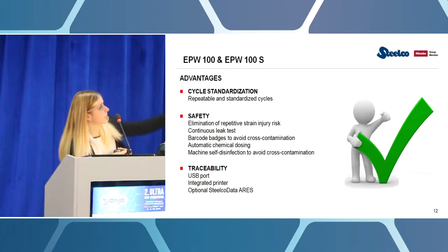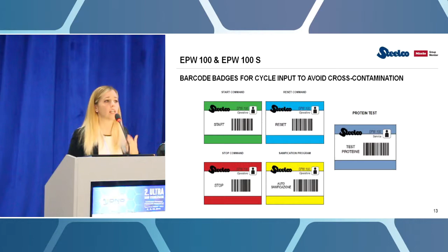And you have a double choice here. You can either communicate with the machine through the display, or, in an attempt to avoid cross-contamination, considering that your hands are dirty in this specific stage of endoscope reprocessing, we developed these badges that can then be washed inside the endoscope washers, so that you're avoiding touching the machine itself. You're not contaminating anything, you're just using these badges that are read by an integrated barcode reader in the machine to communicate with it, go ahead with the cycle, stop the cycle, or do, for example, the auto-sanitation, the self-disinfection of the machine, and so on.